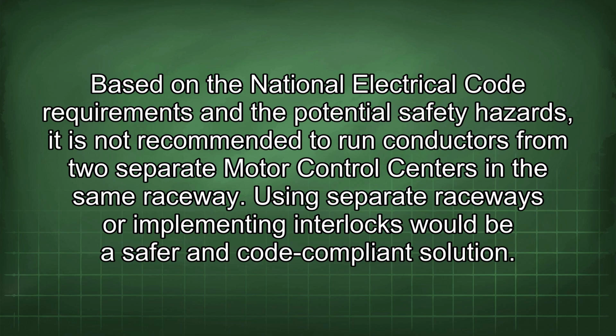Based on the National Electrical Code requirements and the potential safety hazards, it is not recommended to run conductors from two separate motor control centers in the same raceway. Using separate raceways or implementing interlocks would be a safer and code-compliant solution.